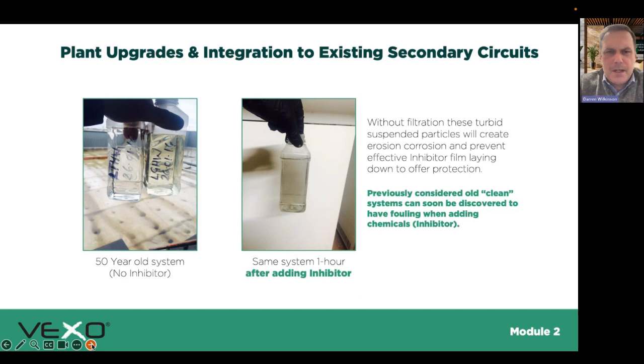The other thing to consider is plant upgrades and integration. Some people expect that if they've installed a new boiler or heat pump and added it to the system, they can still achieve a BSRIA standard for that old system. Honestly, that's pie in the sky. Hitting a BSRIA standard for new systems is one thing, but with a 50-year-old system you're connecting to, you likely won't achieve it. Manage expectations, because maintaining water quality in that sort of system is very challenging.